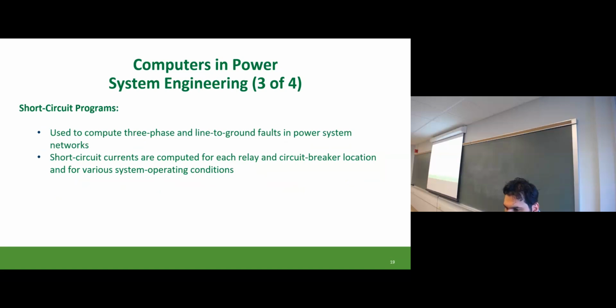Short circuit programs are very important because most of the time people don't care about normal grid operation—they get concerned mainly when a fault happens. This is where short circuit analysis is needed, so we can investigate how bad the fault would be and what protection schemes are necessary.